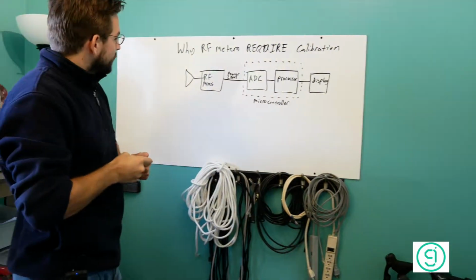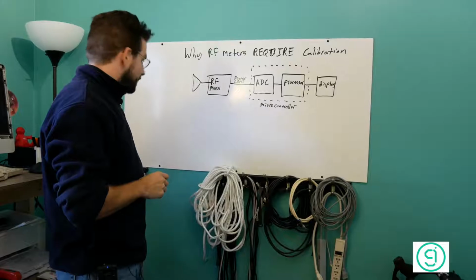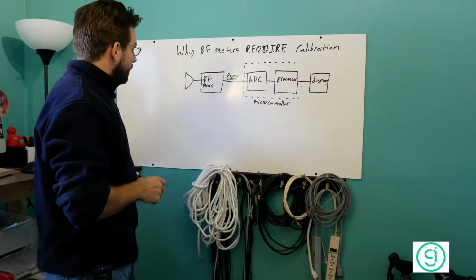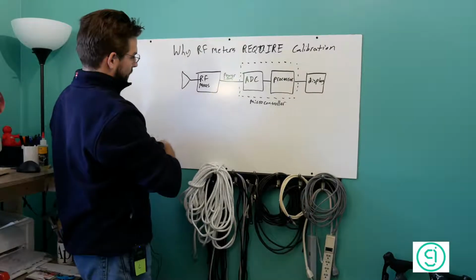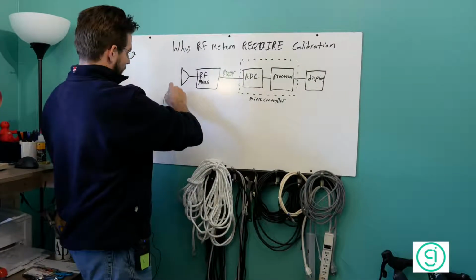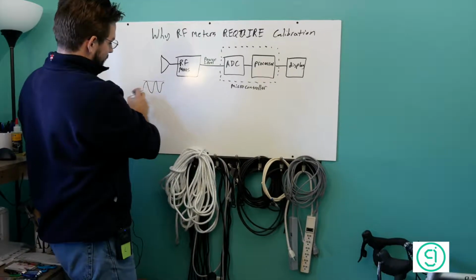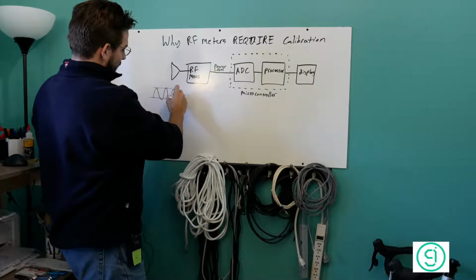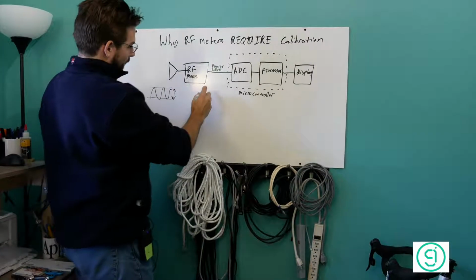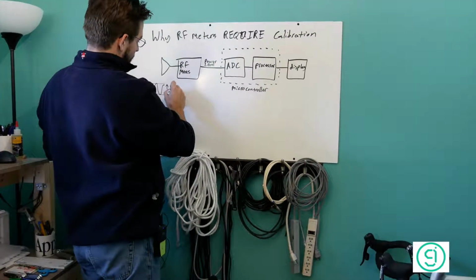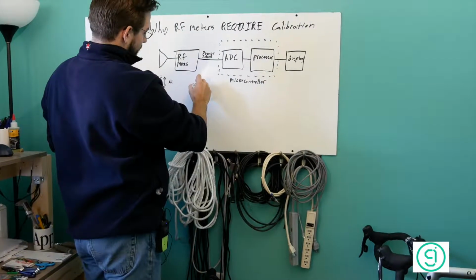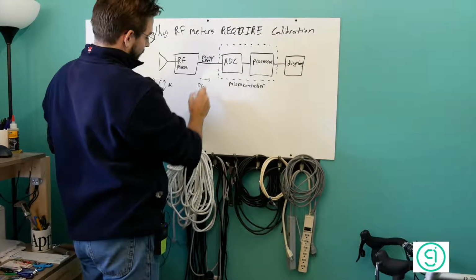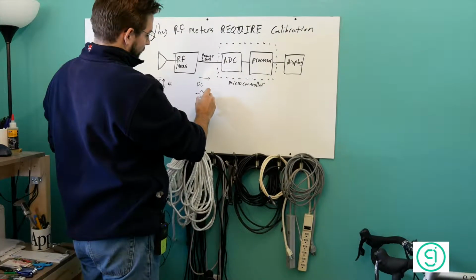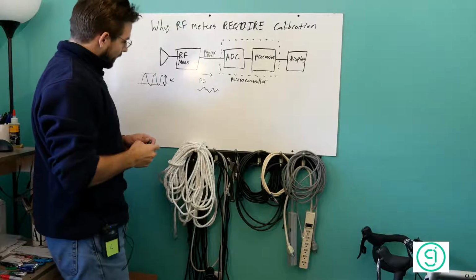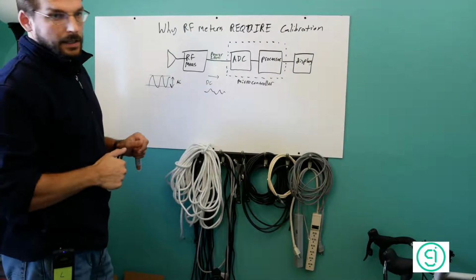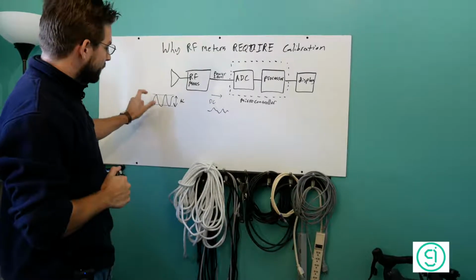All right, so why do you need to calibrate your RF meter? Well, your RF measurement chip takes some power level. You have your RF coming in, and it's some sort of waveform. It measures the amplitude of that waveform, and then it converts it. So on this side it's AC. On this side you get a DC output going to your microcontroller. And it's some voltage level, and it goes up and down based on the amplitude of the AC input. So this would be the amplitude of your RF.